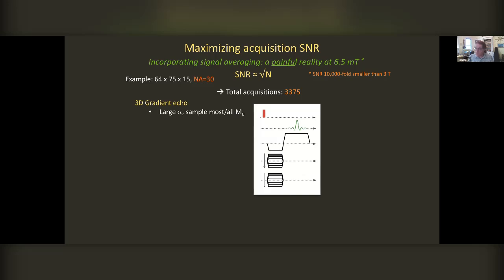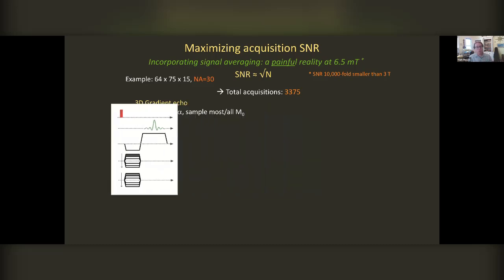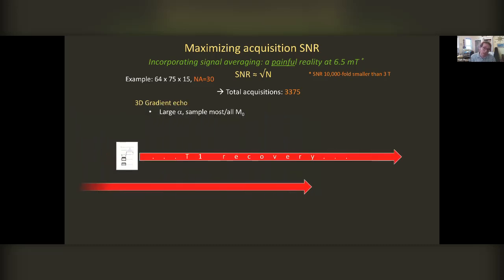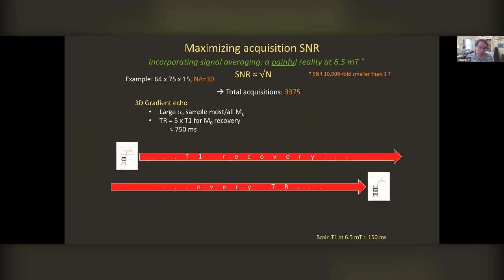That's about 3,400 total acquisitions. And let's just look at the sequences you all know about and how well they work at ultra low field. Well, a gradient echo is great. You do a 90-degree pulse, right? And then you wait for thermal recovery and you do another 90-degree pulse. T1s are shorter at low field, so that helps a little bit, but it's still around 750 milliseconds per shot. And so that acquisition time takes 40 minutes.